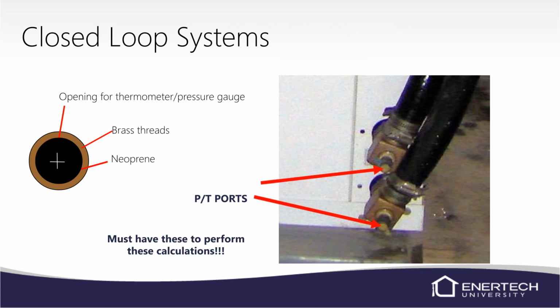Closed loop systems, anytime you've got a pump and dump or the pressurized flow center, or actually the newer non-pressurized flow centers, we can get proper water flow with pressure drop. Some of the old QTs weren't real accurate with their pressure drop across it, so we really couldn't use it. But with the new NP series, variable speeds and things, those pressure drops will work with PT ports. So make sure you have the PT port, you've got to have them. You call in, don't have it, I'm stuck in the mud. We can look at temperature difference, but that doesn't really mean anything because that's obviously going to be affected by the amount of water that you're flowing.